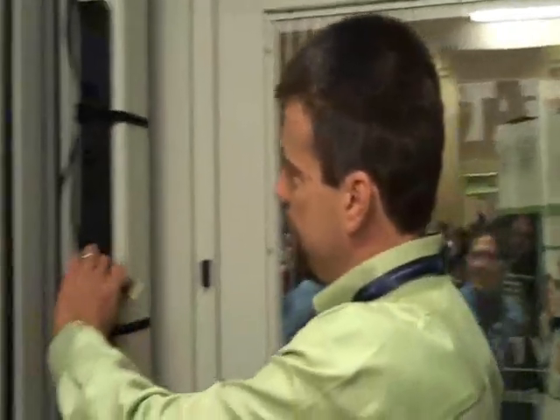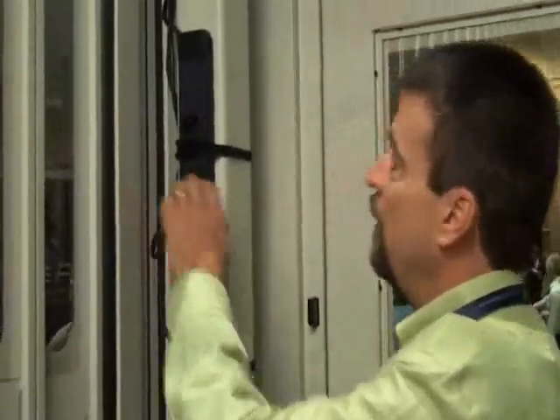And what I'll do is demonstrate that by plugging in a hair dryer, which will blow on a fusible link, and we'll actually see the ceiling of this structure open up to the free space. So with that, now the fusible link is being heated up by the hair dryer, and that hair dryer, as it heats the bimetallic material, will release the link. Once that link is fully released, it'll activate spring energy. That spring energy at that time will cause the ceiling to open.